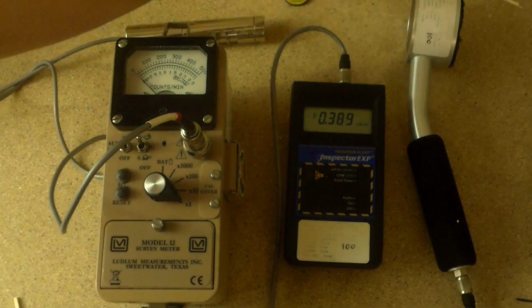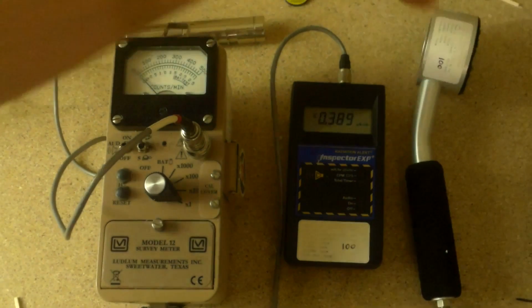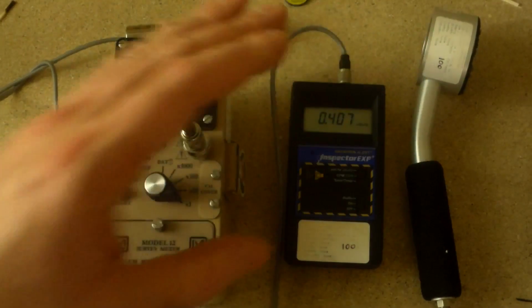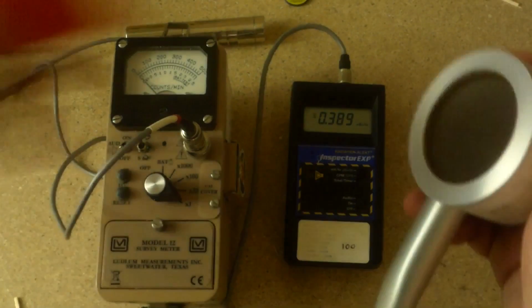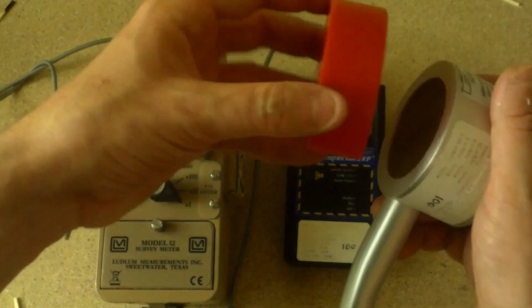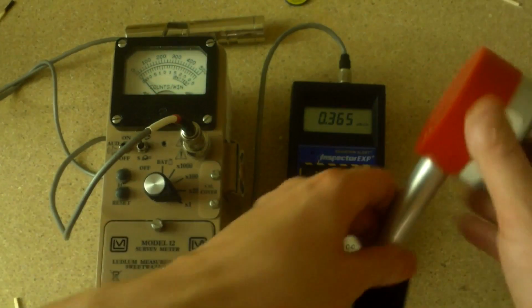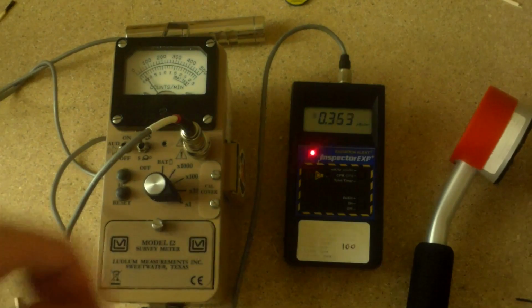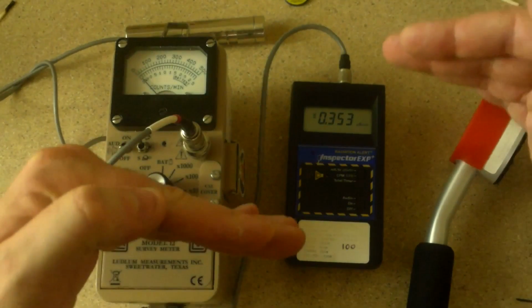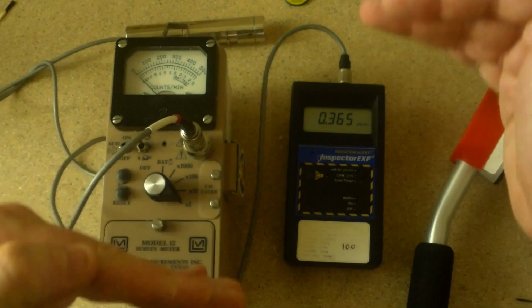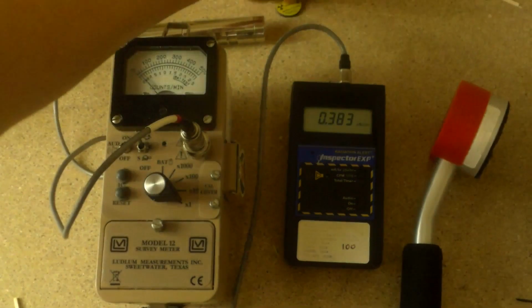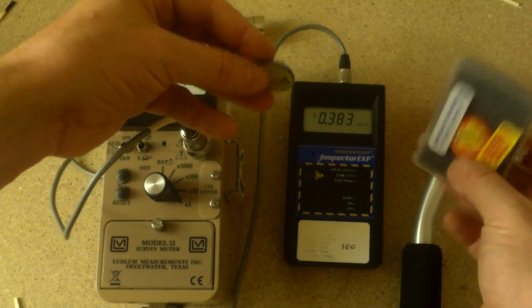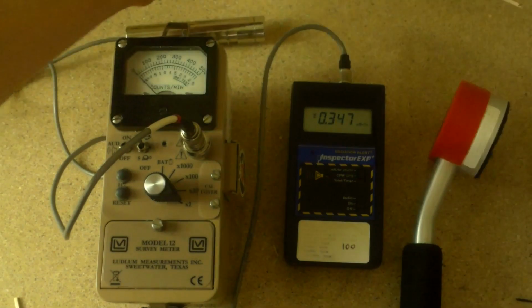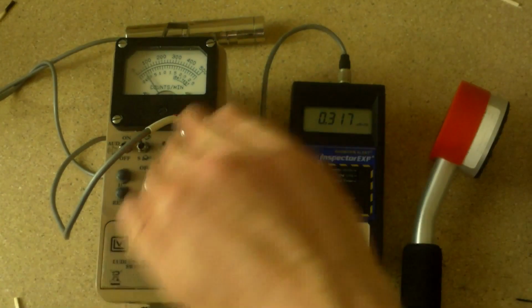Now, some of these types of detectors, not this one, have been specially designed to deal with this exact problem. Sometimes they have a little device put over the front of them. That's not what this is, but they look similar to this. I'm just going to put this over. They're energy compensated. What they do is they have a material in front of them that changes the sensitivity based on energy, to make two completely different radionuclides that have two completely different energies read approximately the same. They flatten that whole sensitivity with respect to energy curve out a little bit.